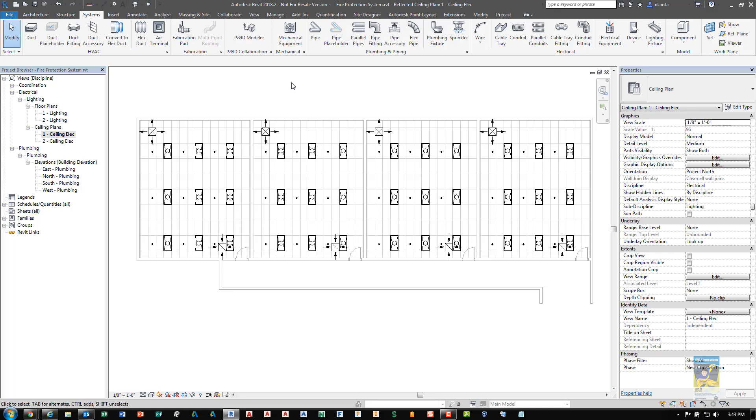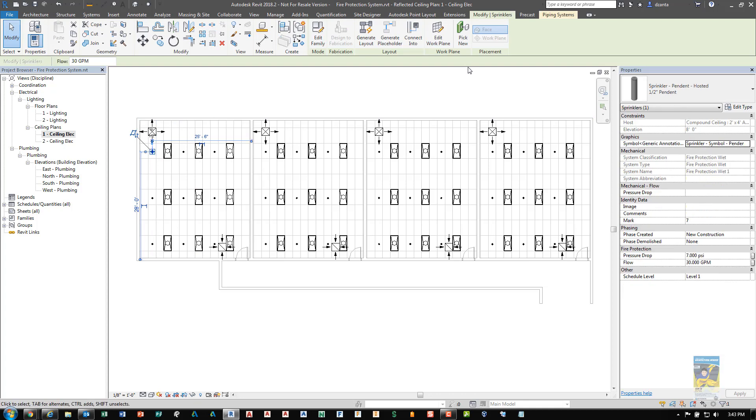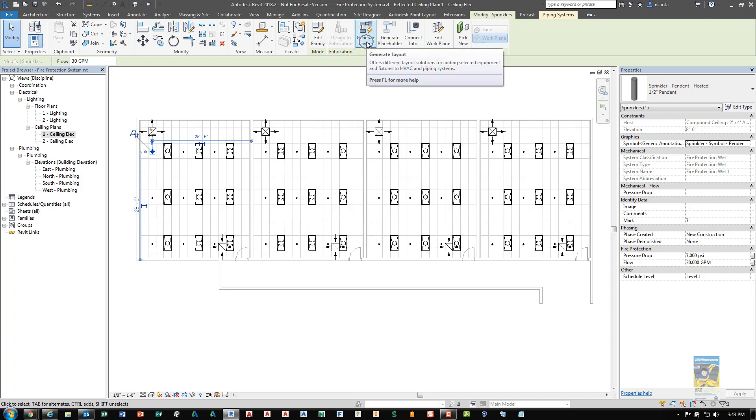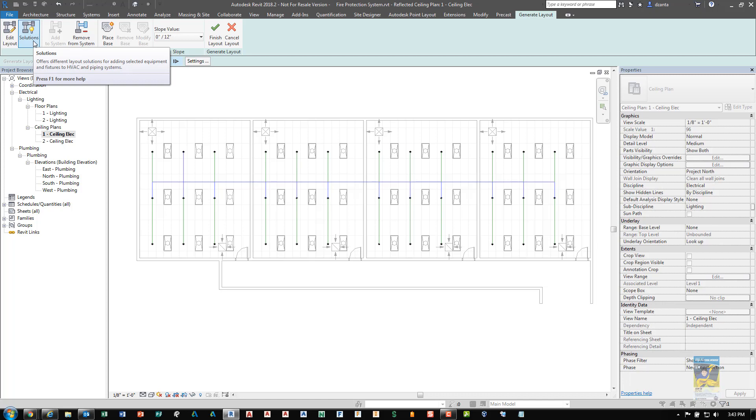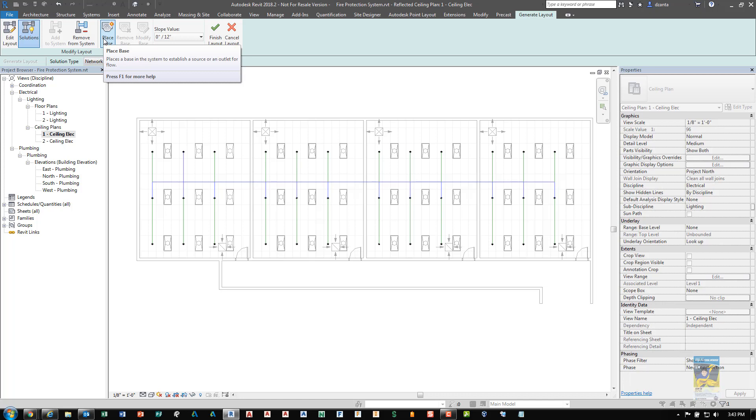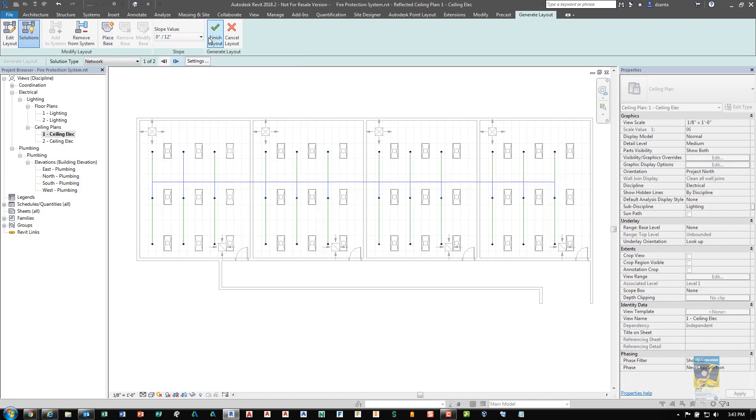And now we need to tell the software, create the system automatically. So that way we don't have to manually draw all of the pipes from the base point of where the water source is to all of the sprinkler heads. So I can pick any one of the sprinkler heads again. And now you'll notice in the modify sprinklers contextual tab under the layout panel, there is the command generate layout. So I'll start the command. And you'll notice that you have solutions, the ability to edit the layout, removing from the system, placing a base water source, specifying a slope, and then finishing the design.